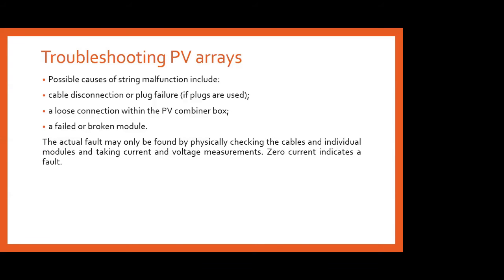And how to check, that is, troubleshooting your PV arrays. The possible causes of a string malfunction can include a cable disconnection or a plugging failure. If any one of the plugs has been unplugged, or if there is a failure with the connection, then the first thing we have to check is the cable connection itself, or a loose connection within the PV combiner boxes also. If there is any loose connection within the PV combiner boxes, we have to check. Then a failed or broken module. The first thing is the mechanical check, which can be seen by observing the PV arrays properly, starting from your cabling and everything. We have to check if there is any problem with the malfunctioning of your PV arrays.